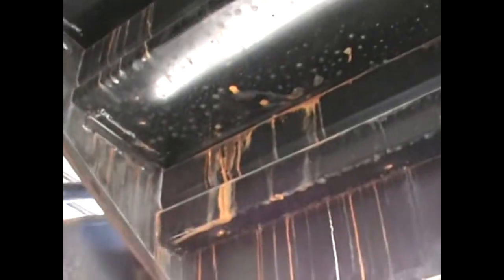And look straight up now. Look at all the rust coming down on you. Yep. We're not walking up anymore, because even though this is a 10-year structure, they're not doing their job. Here's the job that needs to be done: I just cannot seal that and rebolt that. I have to cut the welds, remove the angle, clean it underneath, spot prime it, silicone shut it, and rebolt it back, because I can't weld it back into position. That's amazing. Okay? And this is only 10 years old.